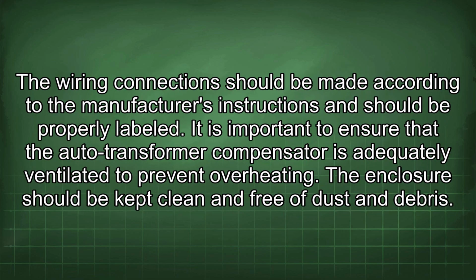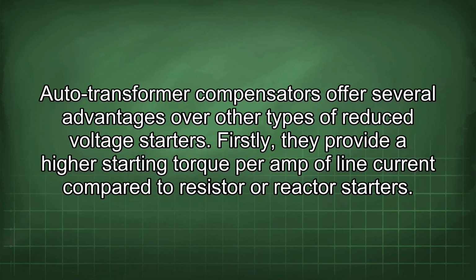The wiring connection should be made according to the manufacturer's instructions and should be properly labeled. It is important to ensure that the autotransformer compensator is adequately ventilated to prevent overheating. The enclosure should be kept clean and free of dust and debris. Autotransformer compensators offer several advantages over other types of reduced voltage starters.